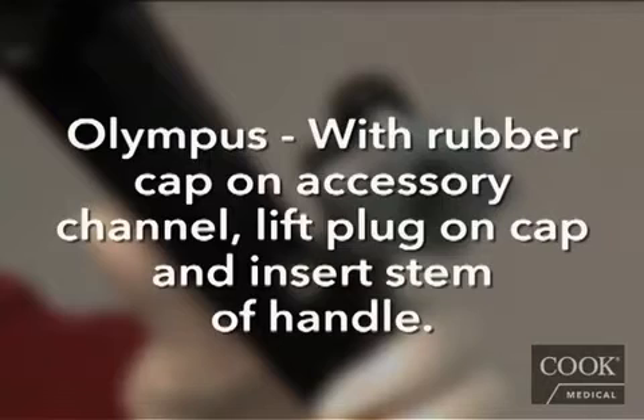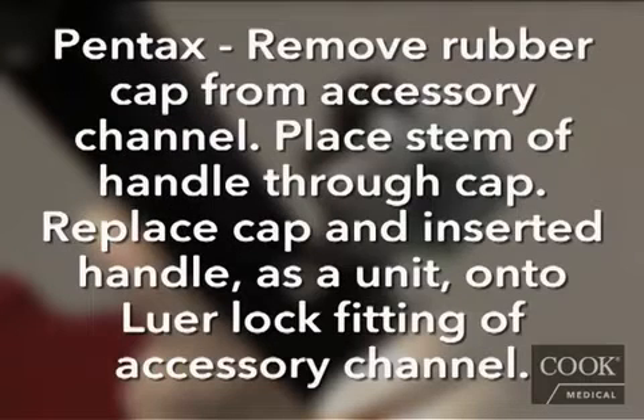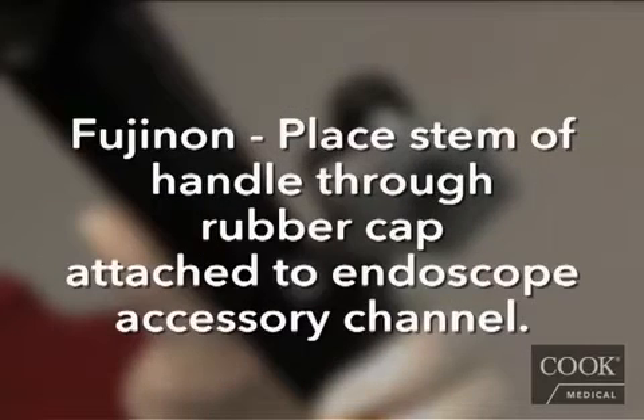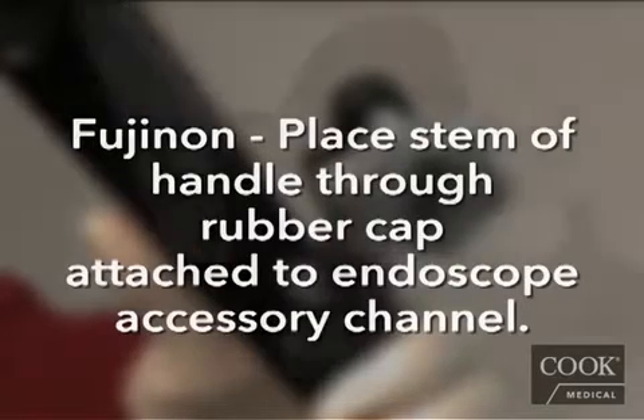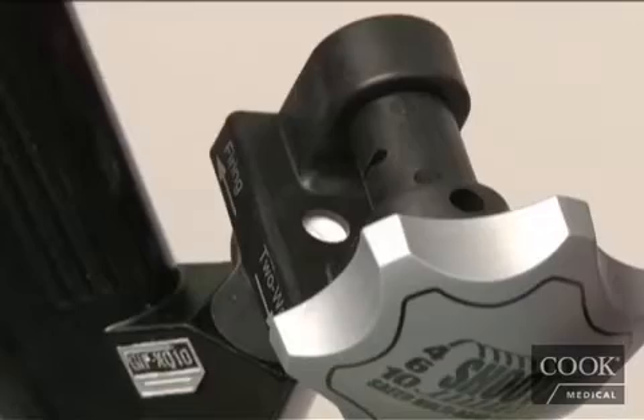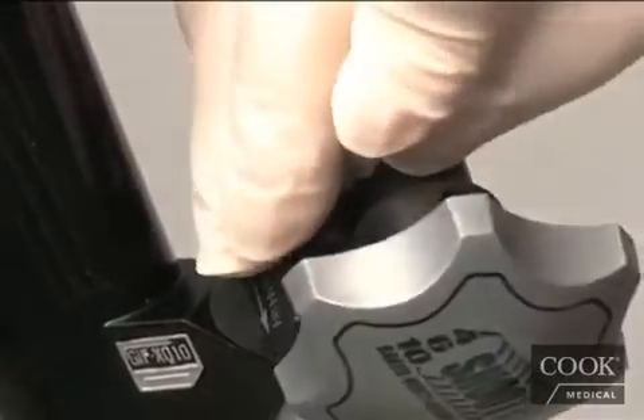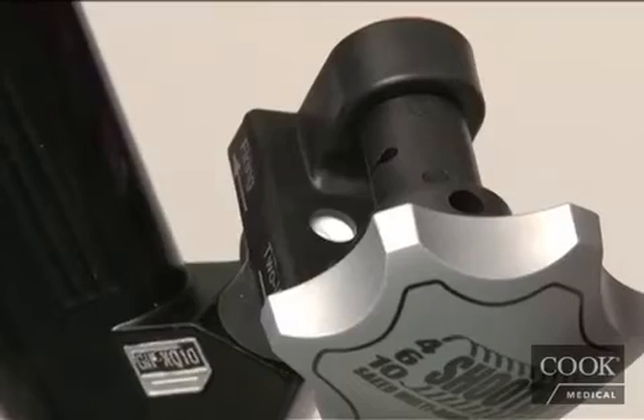For Olympus, with rubber cap on the accessory channel, lift the plug on the cap and insert the stem of the handle. For Pentax, remove the rubber cap from the accessory channel. Place the stem of the handle through the cap. Then replace the cap with inserted handle as one unit into the luer lock fitting of the accessory channel. For Fujinon, place the stem of the handle through the rubber cap attached to the endoscope accessory channel. Note, the irrigation adapter may be used to puncture the white self-sealing valve prior to introducing the loading catheter.